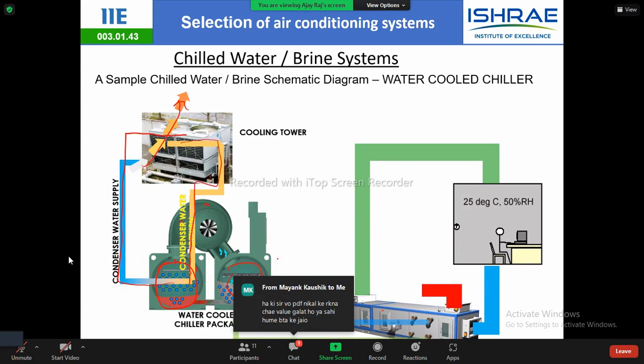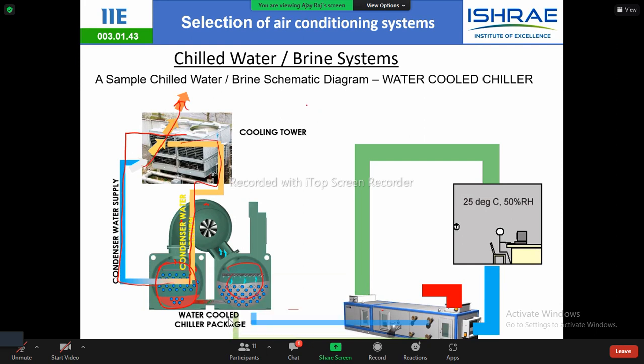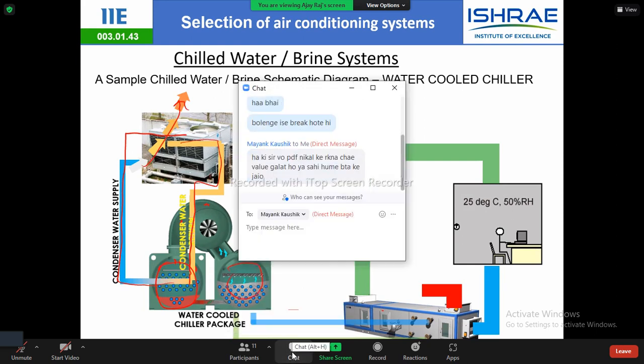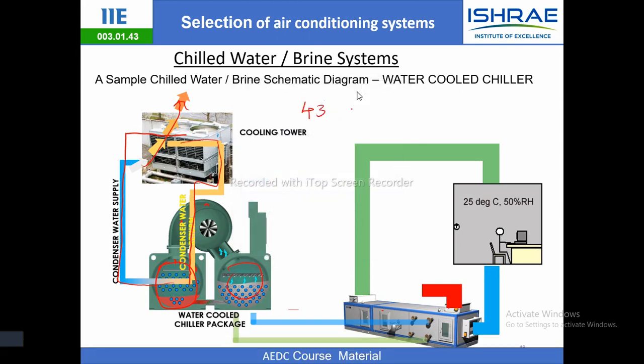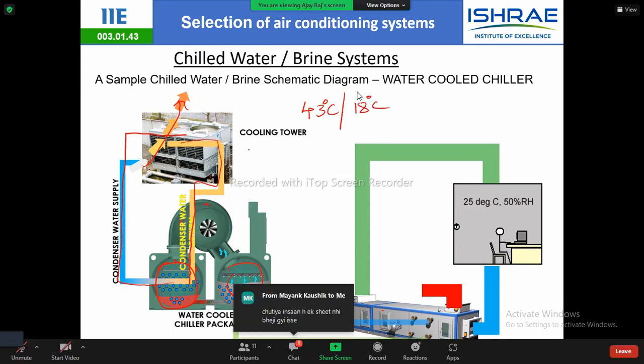So what happens is, if I have an air cooled chiller, it rejects heat at ambient temperature. Let's say we're talking about peak summer, and in Delhi it is 43 degrees centigrade and your wet bulb temperature will be 18 degrees centigrade. So in case of a cooling tower, you'll be rejecting heat very close to 18 degrees centigrade. In air cooled, you'll be rejecting heat to 43 degrees centigrade. That's why most of the time you will see that your water cooled systems are more efficient as compared to your air cooled system. I hope it is clear.